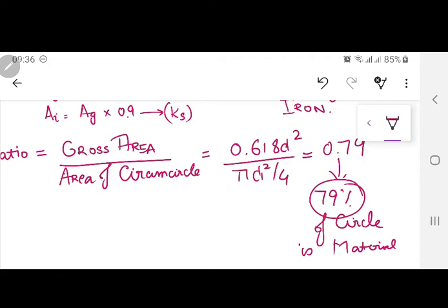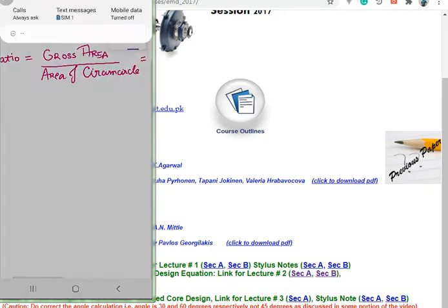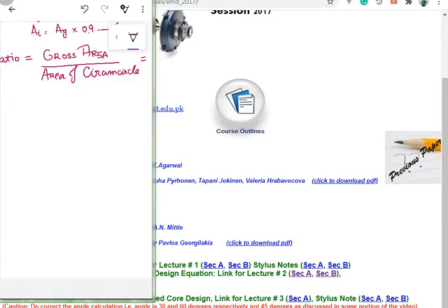So if you are a very bad manufacturer, your material is not good, and the laminations are also not uniform. This is very important. Maybe in the next few classes I will open one transformer in front of you. If the laminations are not uniform, when you stack them together there will be some air gap. That air gap also contributes to a lower stacking factor. So stacking factor is dependent upon your workmanship, your material also, and certainly how you are stacking those sheets. So this one, always in short, I'm just going to turn this off.